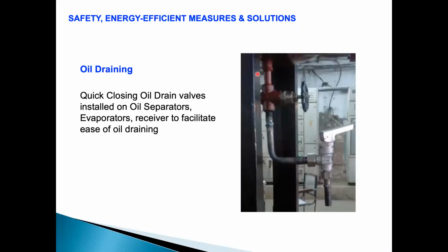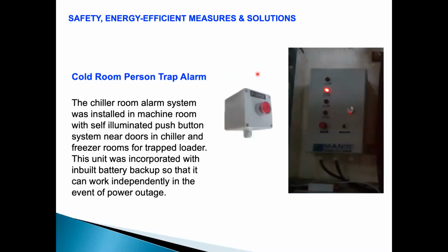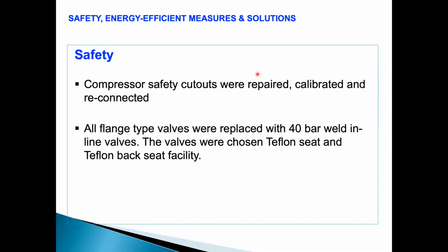All the drain systems were connected with a dead man's valve or the oil drain systems. Ammonia detection system was installed on wall stations in the cold rooms, so that in case of any leakage, you get an ammonia indication. For avoiding man trapping, the loaders getting trapped in the cold room, man trap alarms were installed. Compressor safety cutouts were repaired, recalibrated and reconnected. All controls were made functional.